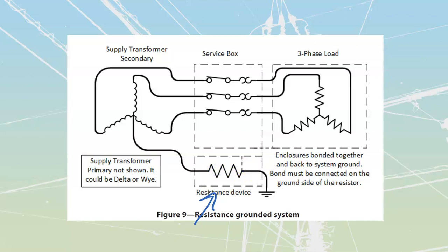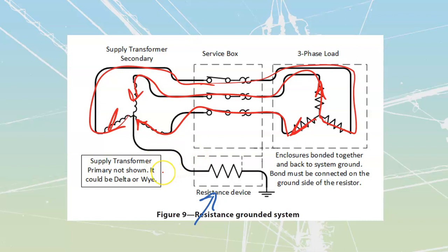Normally I should have no current traveling through this resistance. If I take a look, all the current I'm delivering out—let's say A is high, that would mean B and C are opposite and halfway in the opposite direction. So my A current splits, comes back in through here and here, and rejoins over there. So nothing travels through this ground conductor itself. With 0 amps traveling through something, according to Ohm's law, V equals I times R, and if current is 0, the voltage dropped across is also 0. So this is 0 volts when we don't have any fault current going through it. This means that with 0 volts drop between the ground and the neutral, our neutral is also at that same 0 volt point.